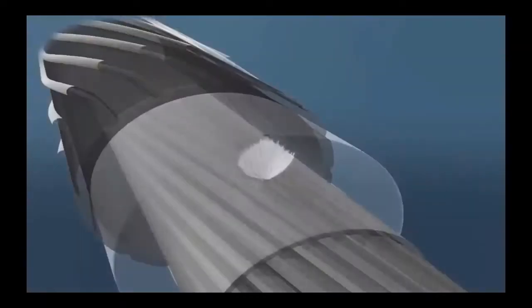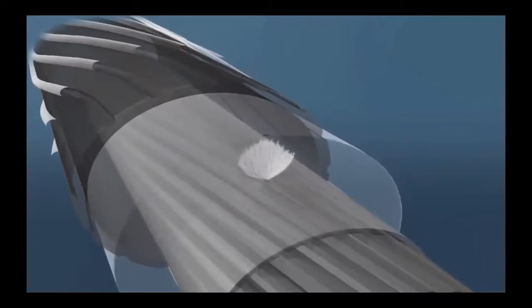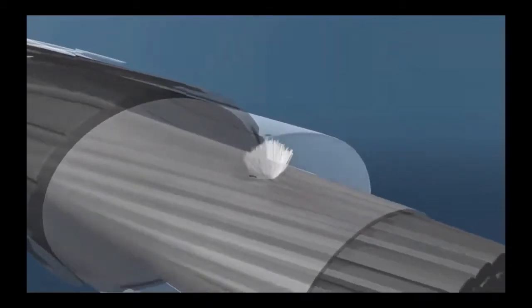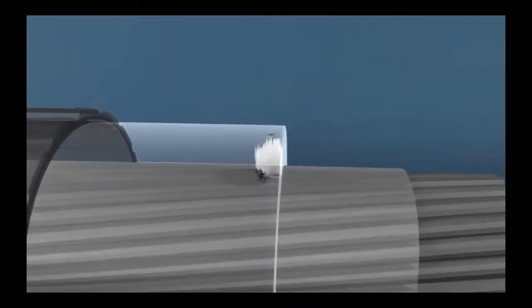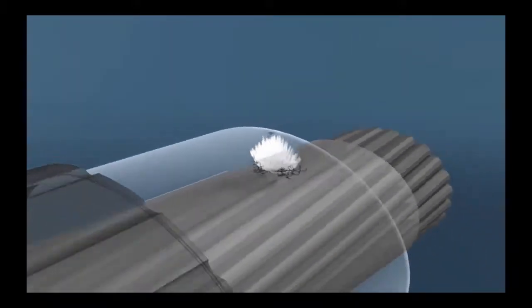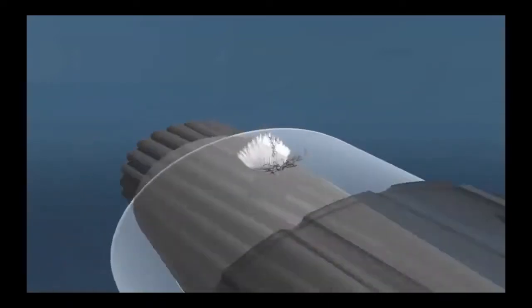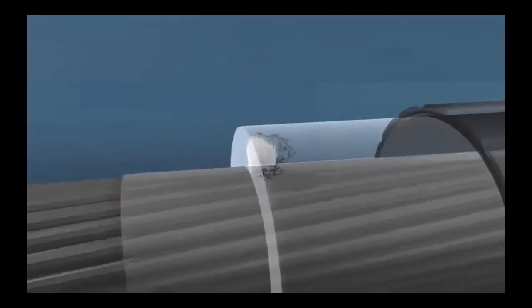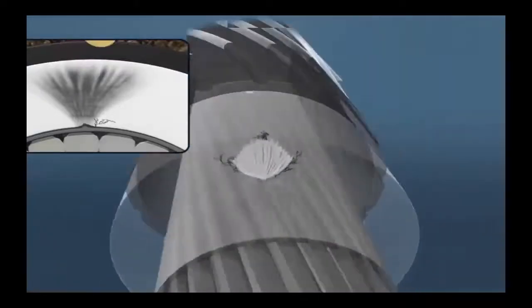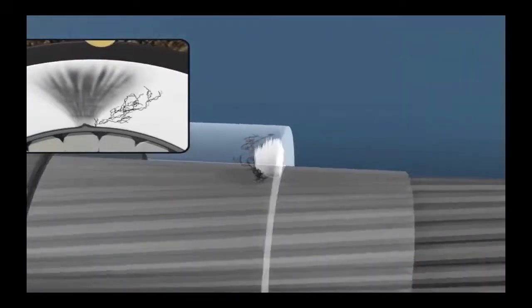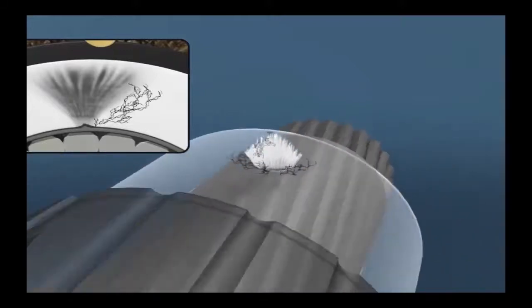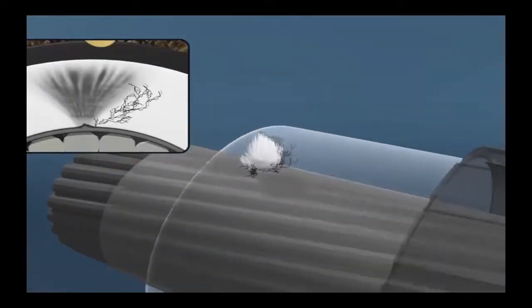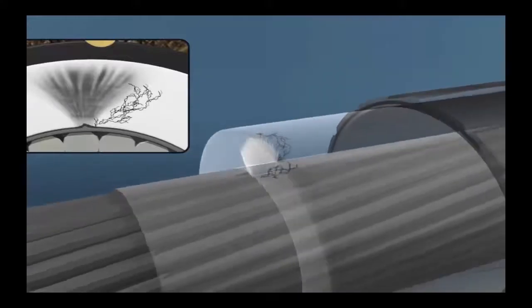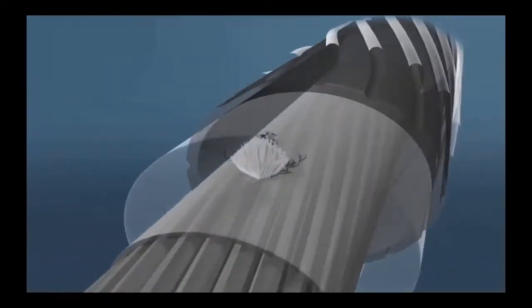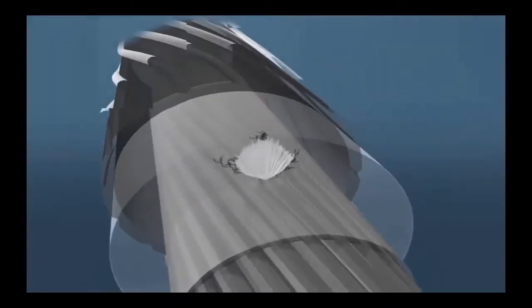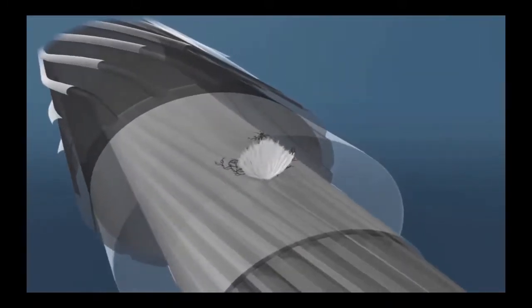So we're going to make this insulation transparent. And we've seen a lot of cross-sectional areas, but here you're able to put a lot of these cross-sectional areas and pictures together to get a three-dimensional picture of what this looks like. Here we show where the carbon tree is going over and around the water tree, which is something new. It's never been seen before. We introduced this to ICC last year, but it just proves the path of the carbon tree when it's accompanied by a water tree. It's kind of like a gift and a curse because it makes the cable last a little bit longer, but ultimately it will go to failure as long as it's seeing bad and transient voltages.